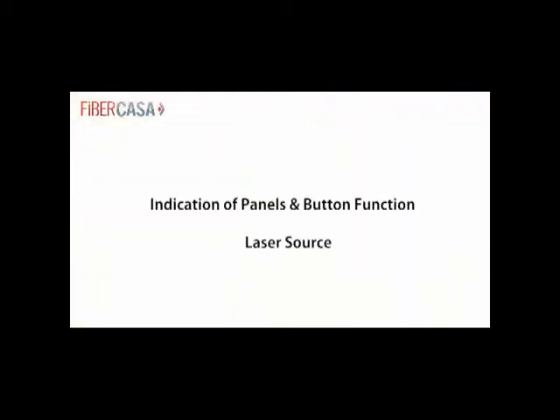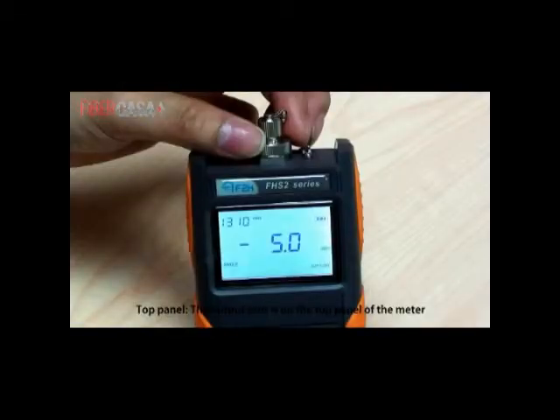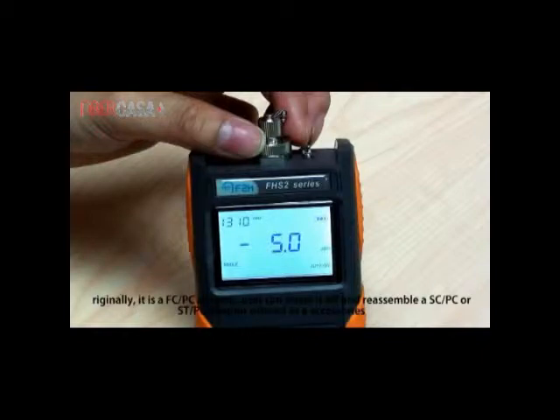Indication of Panel and Button Function - Laser Source Top Panel. The output port is on the top panel of the meter. Originally it is an FC-PC adapter. Users can screw it off and reassemble a SC-PC or ST-PC adapter offered as an accessory.